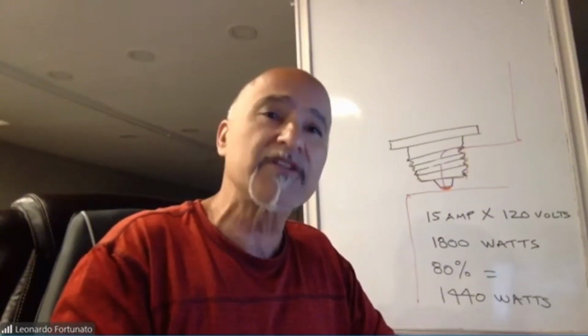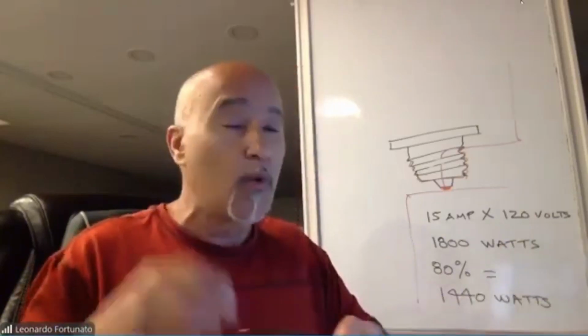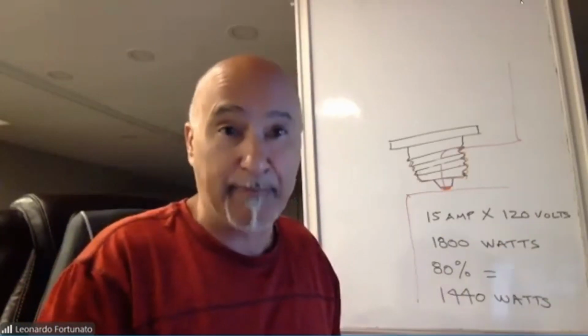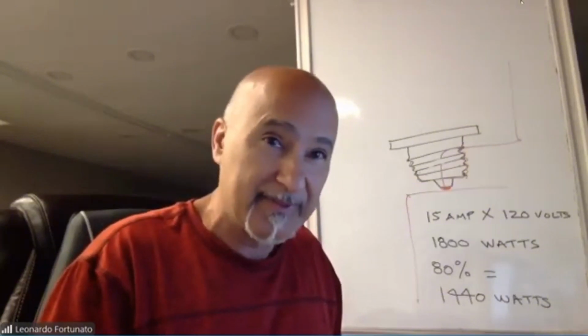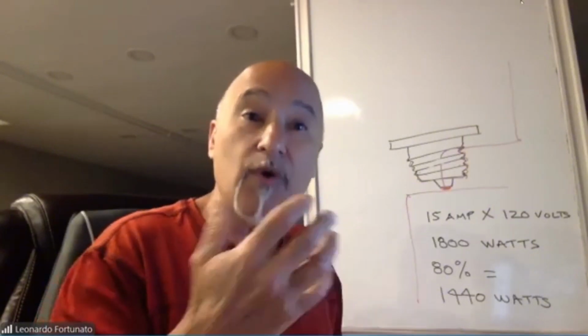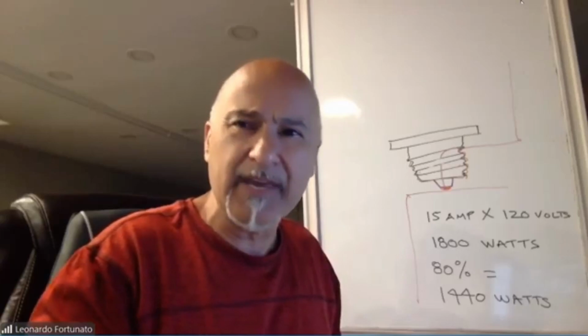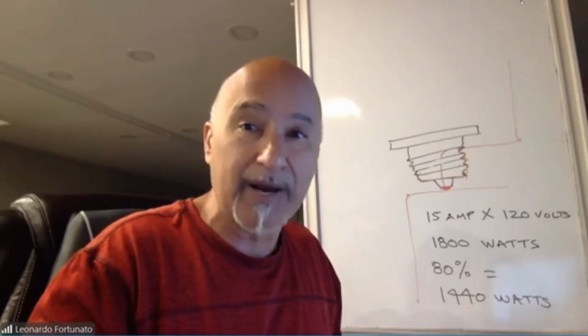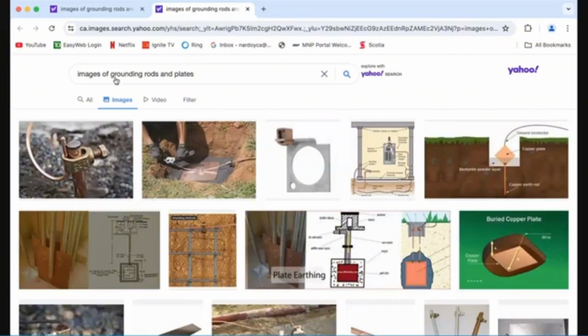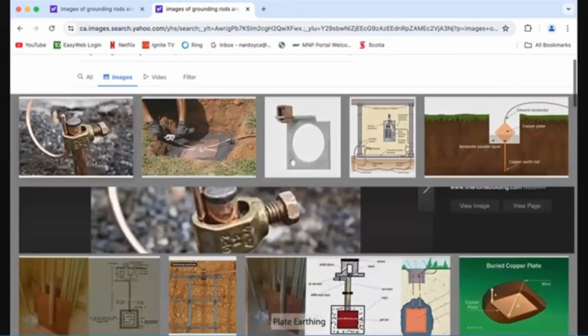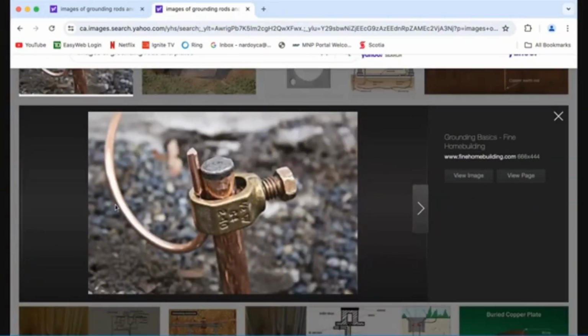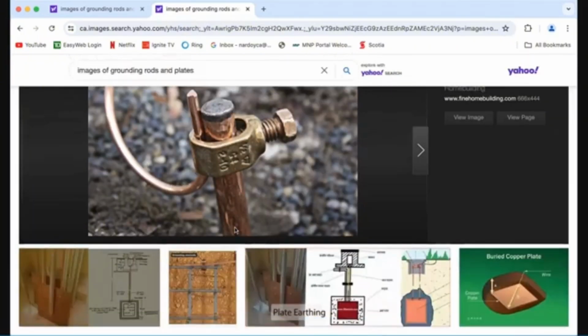For example, if we have a different type of pipe, a plastic pipe that brings the water into the house, we're not going to bring the ground wire to that pipe because it's not metal. Then we would need to use a grounding rod or a grounding plate. Let me give you a good example of a grounding plate. If you look at this first image, this is the top of a grounding rod. Here's the ground wire. This is a lug. We secure the wire to this rod. That rod will be 1 inch in diameter, 8 feet long, and we drive that into the ground.